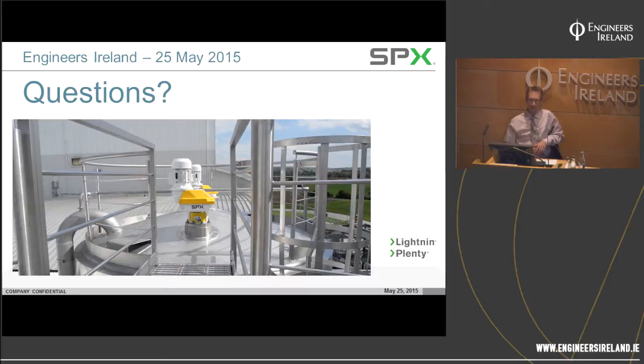My concern at the time was that if the central plume was going up, the agitator was trying to bury itself in the liquid and trying to self-center. And a few years later, the shaft bent. I suppose my question is, seeing this issue actually playing out, if you did have a situation where you had the central plume rising, i.e. the agitator is trying to pull itself into the tank, where would you inject the chemicals?